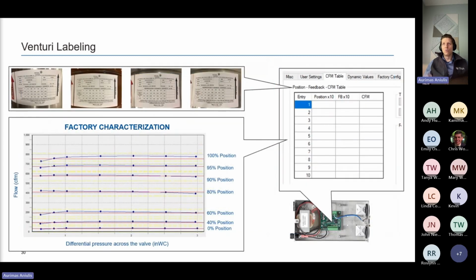So when we look at factory characterization, this is what every single valve that we produce comes with. It comes with a chart showing that at 0 position, it maintained its flow throughout its entire pressure range. And all the way up to 100%, it shows that it maintained its CFM regardless of duct static pressure swings, plus or minus 5%. That data gets linearized and put into a simple lookup table inside of our UVM PCBA here, which is mounted on each valve. That's our valve brain. And it's a very simple lookup table, meaning here's the position, here's the feedback, and here's the CFM. And the same information is basically found on the labels attached to each valve.